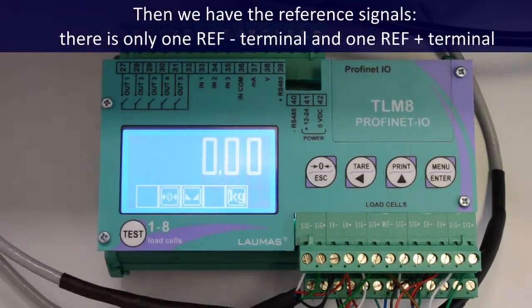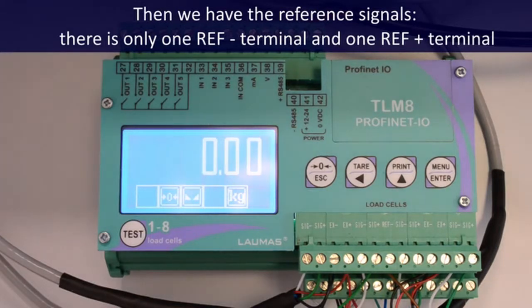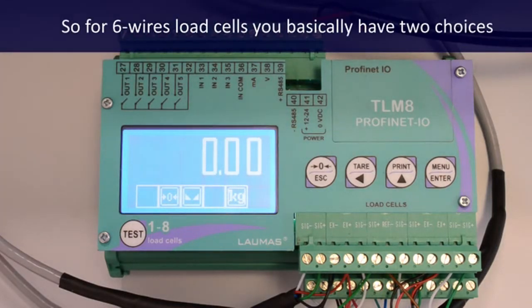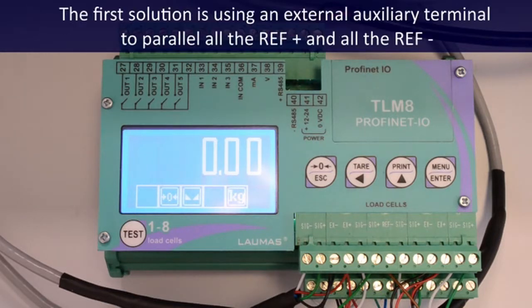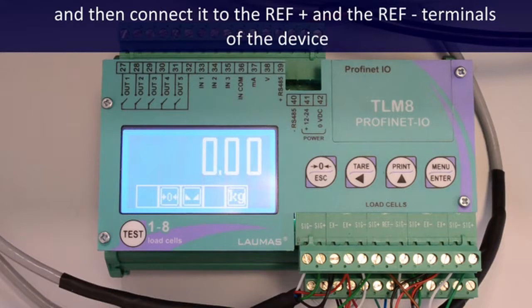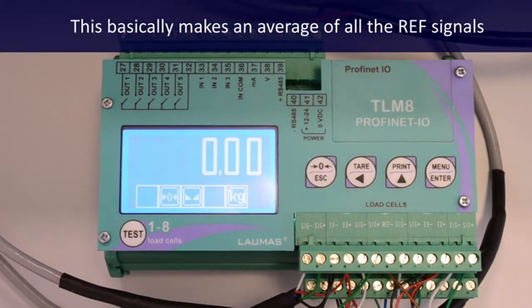Then we have the reference signals. There is only one ref minus terminal and one ref plus terminal. So for 6 wire load cells, you basically have 2 choices. The first solution is using an external auxiliary terminal to parallel all the ref plus and all the ref minus, and then connect it to the ref plus and ref minus terminals of the device. This basically makes an average of all the ref signals.